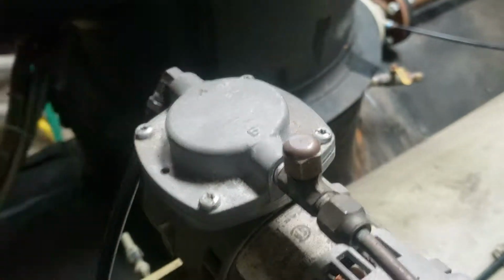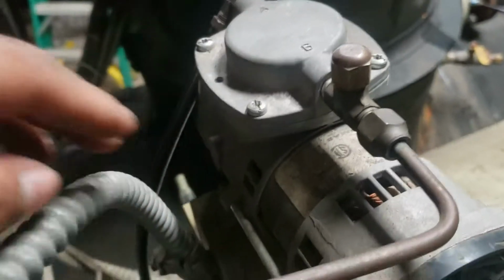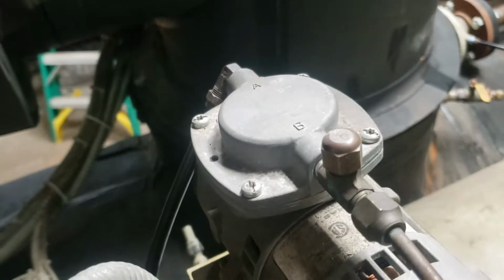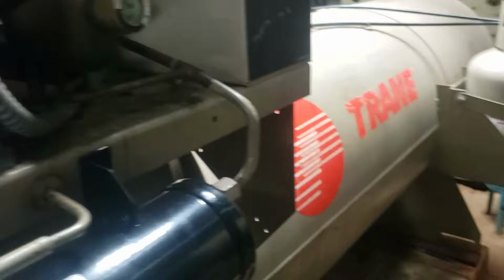Sometimes there'll be a restrictor in here somewhere, a restrictor right here. Sometimes that will clog up and won't let the air come out. You can put a hose from right here to right there, and that'll bypass your restrictor, and you'll bleed out the air like that, or vent it out. All that's working, so we verify that the purge unit is working.